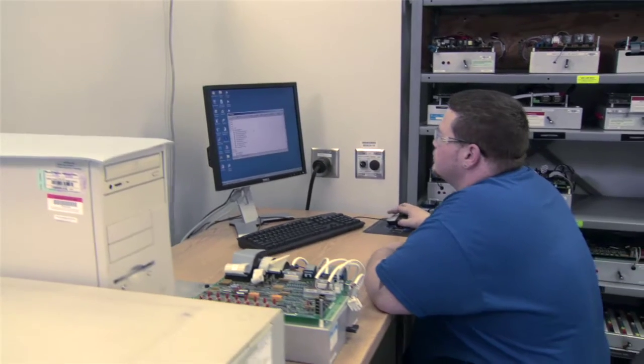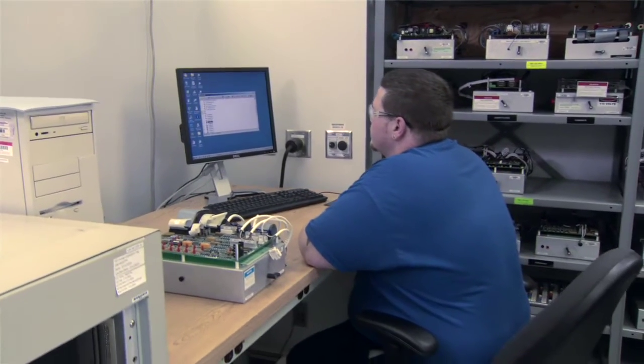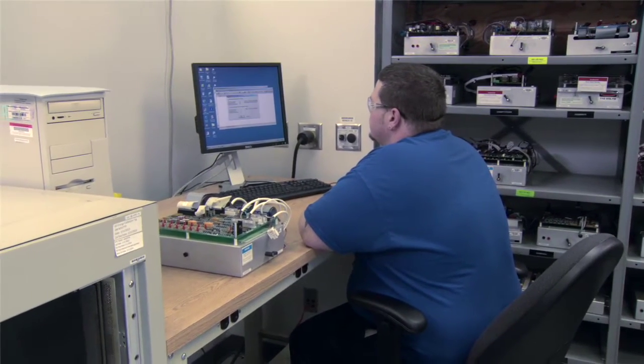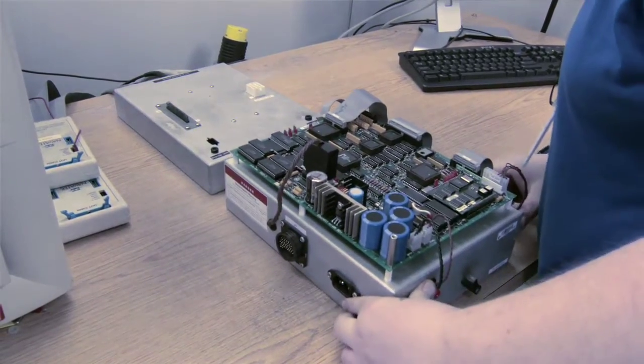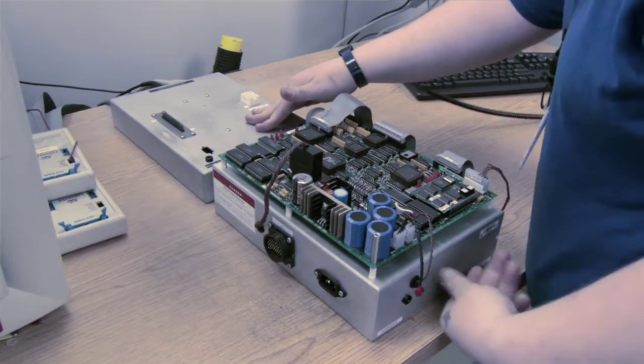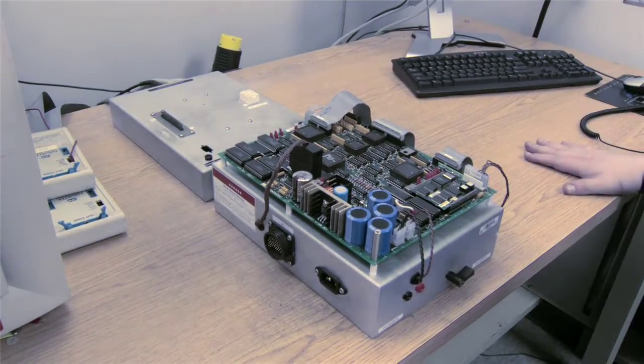At our automated test equipment station, or the ATE, we can test Mark 4 and Mark 5 controls, along with DS200 and DS3800 units. The ATE performs a full functional test that runs the board through all of its variables before we bring it over for burn-in testing.